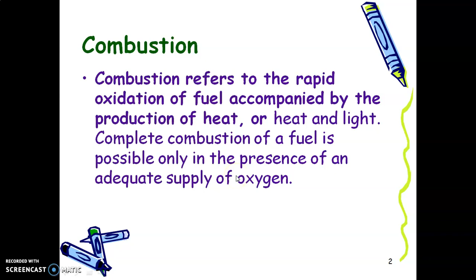What is the significance of any combustion reaction? It helps in finding the correct air supply rate. Flue gases, that means waste gases composition, can be detected for the combustion products. It is an important feature to design, run and maintain a boiler. It gives the complete data for combustion and this in turn helps for the regular maintenance. Therefore, it is important to calculate the amount of air required for combustion.